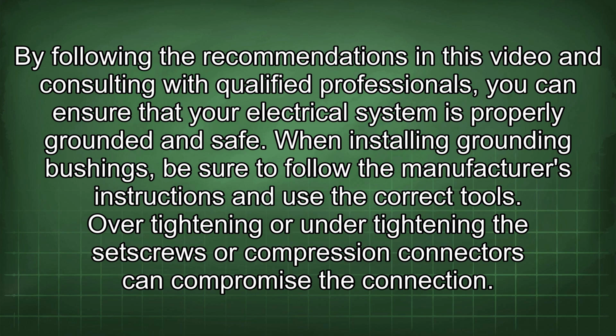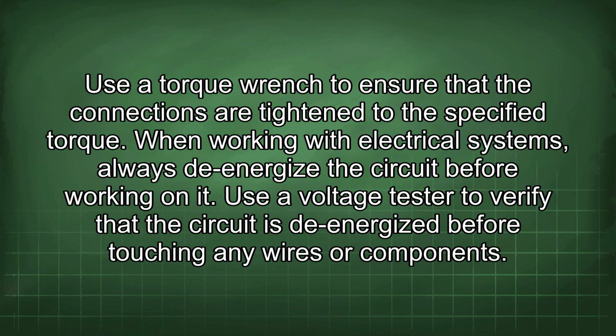properly grounded and safe. When installing grounding bushings, be sure to follow the manufacturer's instructions and use the correct tools. Over-tightening or under-tightening the set screws or compression connectors can compromise the connection. Use a torque wrench to ensure that the connections are tightened to the specified torque. When working with electrical systems, always de-energize the circuit before working on it. Use a voltage tester to verify that the circuit is de-energized before touching any wires or components.